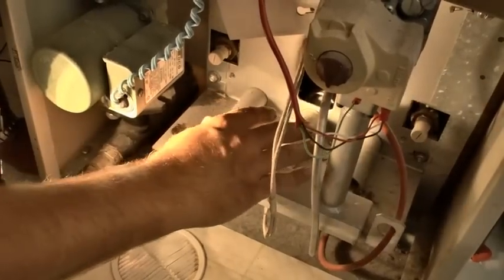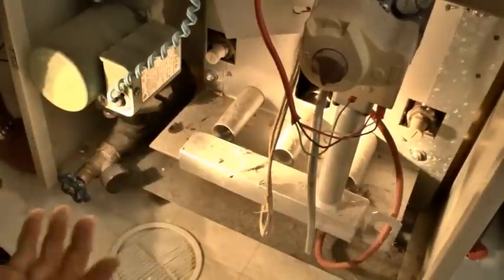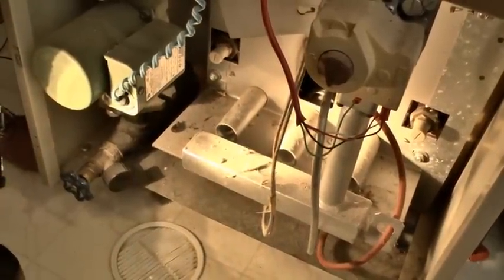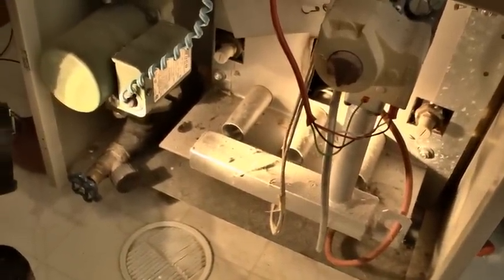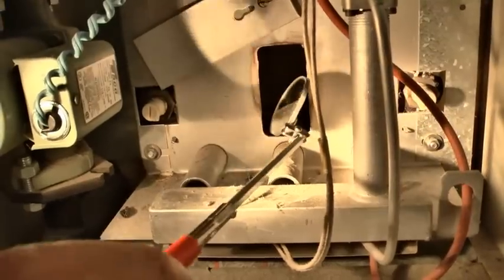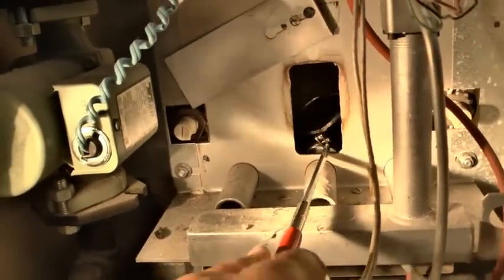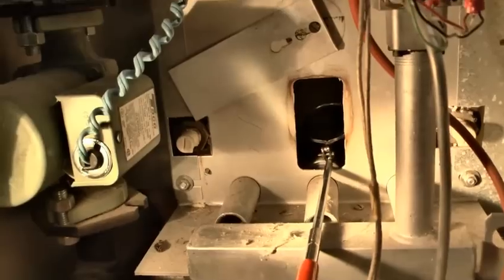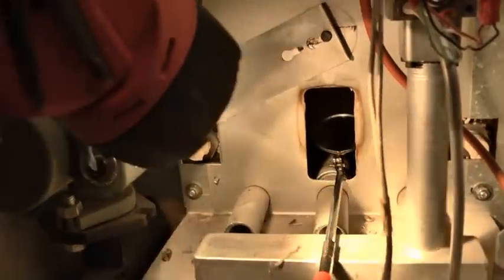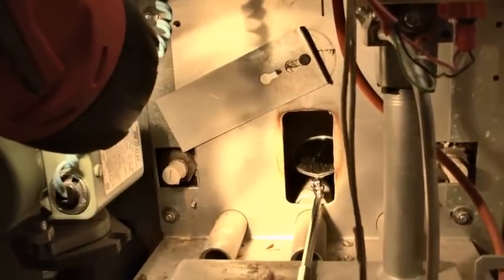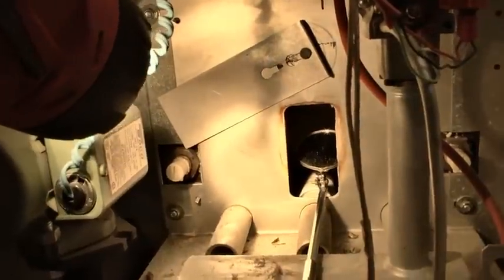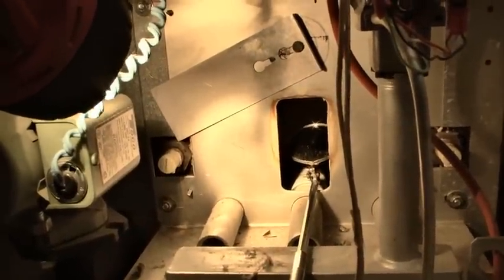So we would clean this all up. We pull the burners, we clean the burners, blow them out with compressed air, vacuum them. Another thing we want to do, you're not necessarily going to see cracked heat exchangers like on a furnace, because if you have a cracked heat exchanger, water comes out of it and you'd have water on the floor. But what we do want to look for is a plugged heat exchanger.